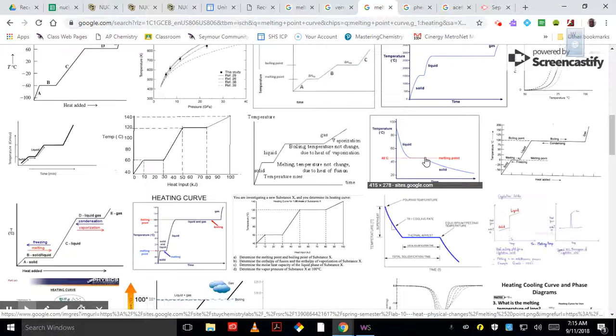which you're going to determine by looking in that little magnifying glass. And as soon as you see the first crystal of the material start to melt, you start recording the temperature. Hopefully, if you have done the recrystallization process correctly, it will remain at that temperature the entire time. If you don't do it too well, or you run the melting point machine too fast, you'll get a range of temperatures.